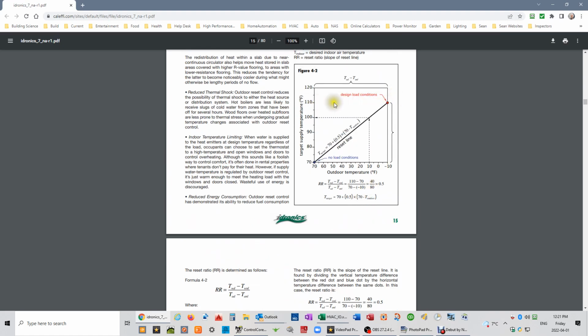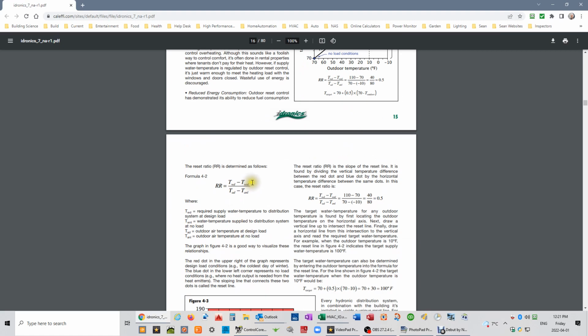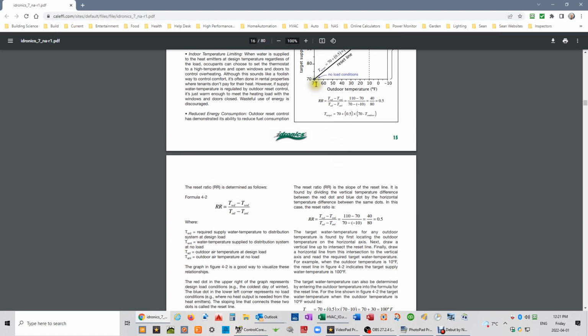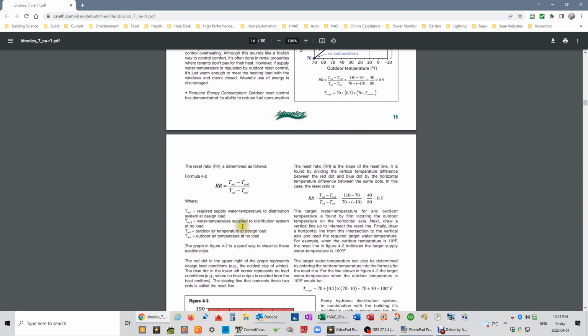So in this case, we're looking at about 110. Take away the water temperature at no load, which would be 70 if it's equal to the 70 room temperature, over top of the outdoor air temperature at design load, so minus 10, take away the outdoor temperature at no load, so again 70. So we've got 110 take away 70, 70 take away minus 10. That produces a reset ratio of 0.5.